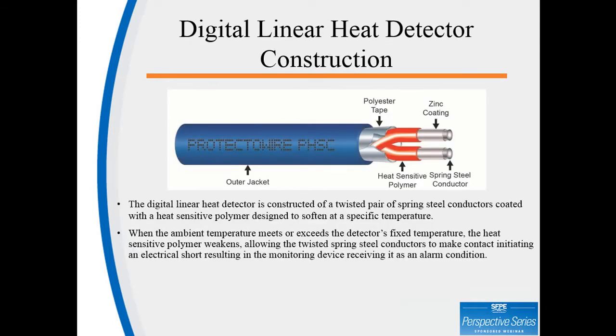Now we're going to talk about digital linear heat detector construction. The digital linear heat detector is constructed of a twisted pair of spring steel conductors, coated with a heat-sensitive polymer designed to soften at a specific temperature. When the ambient temperature meets or exceeds the detector's fixed temperature, the heat-sensitive polymer weakens, allowing the twisted spring steel conductors to make contact, initiating an electrical short, resulting in the monitoring device receiving it as an alarm condition.